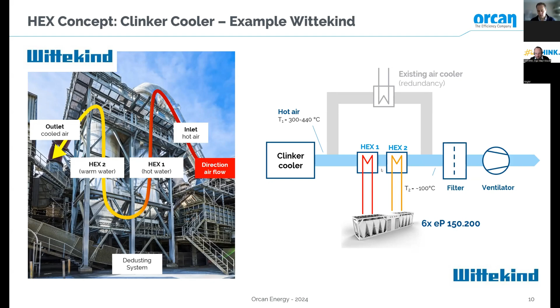You have here the exhaust gas flowing within the pipes. There are 1,000-something pipes or tubes, surrounded by water. The water is heated up, and this heat goes to our machines, where we produce electricity. In this case, we have a 2-stage heat exchanger so that we can cool down the heat as much as possible, with a low temperature loop at 80-90 degrees where we preheat our fluids.